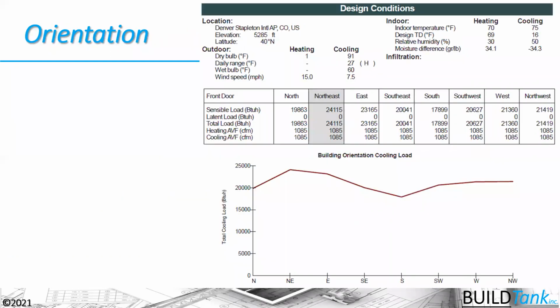So the last two that we have here before we close out are orientation. So orientation, the code doesn't require that we do site-specific and orientation-specific HVAC designs, especially for production builders. So if you do a general design for that house or an estimate design for that house, some people call it a worst-case design, you might have locations where the BTU loads vary a lot. In this case, the northeast orientation of the house versus the south orientation of the house varies by about 6,000 BTUs or half a ton of air conditioning there. So that house could be oversized or undersized depending on the orientation of the house.